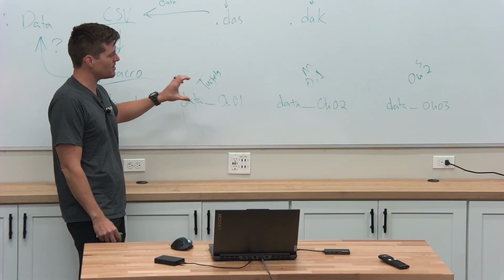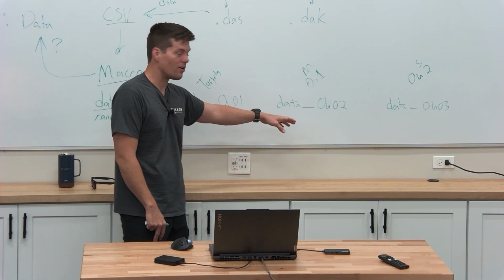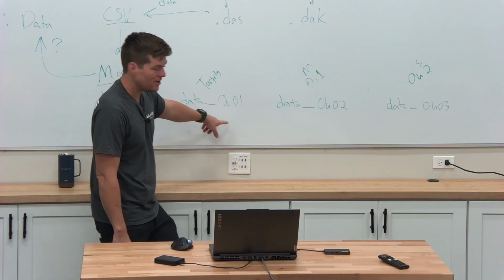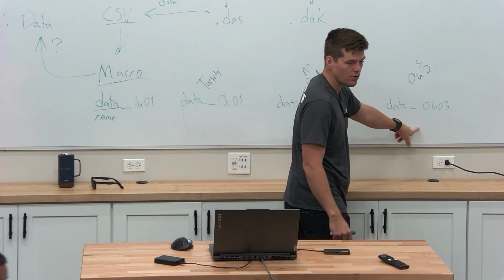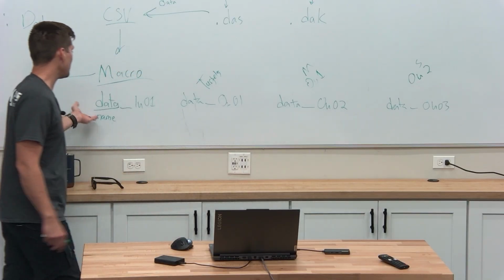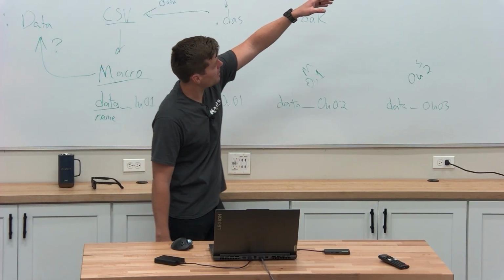It's a spreadsheet. It's designed to take data numbers and plug them in. And if these are out of order and they don't work the way they're supposed to, and you haven't gone in to verify this is your targets, this is your master, and this is your sub, when you use the macro, because indoor units can be in whatever order, it doesn't matter, it's all the same information. But this is your targets, which you can see here: cooling, heating, parallel, thermal on, restart, standby, backup operation. It's got all your targets, your TE, your TC, your target condensing pressure, your evaporator pressure targets.